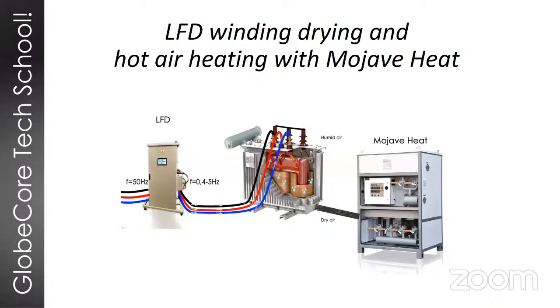Next slide, please. All right, here you can see a combination of LFD with what we call a Mojave heat. Mojave is a very famous desert in the United States, a very dry place, and it's not a coincidence, this name. So this is a hot, dry air blower. Before the process begins, we drain all oil from the transformer tank. The LFD heats the transformer windings, and then we connect the Mojave heat system. We heat the windings with LFD, moisture evaporates into the transformer tank, and then the Mojave heat supplies very dry air into the transformer tank with a dew point of -50 degrees Celsius. The air is hot, and so when it passes through the transformer, it's so dry that it basically carries out all the moisture that has been evaporated from the insulation, and that air is pushed outside. Next slide, please.